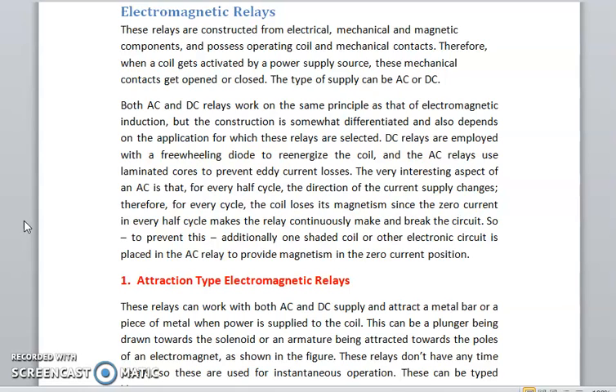Both AC and DC relays work on the same principle as that of electromagnetic induction, but the construction is somewhat different and also depends on the applications for which these types are selected. DC relays are employed with a freewheeling diode to handle the coil's stored energy, and the AC relays use laminated coil cores to prevent eddy current losses.